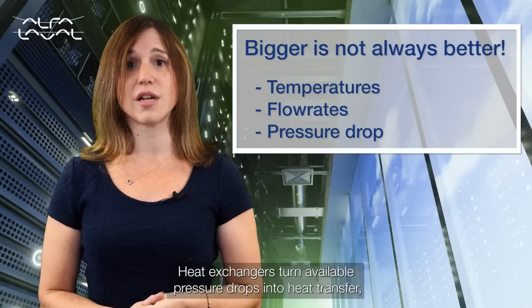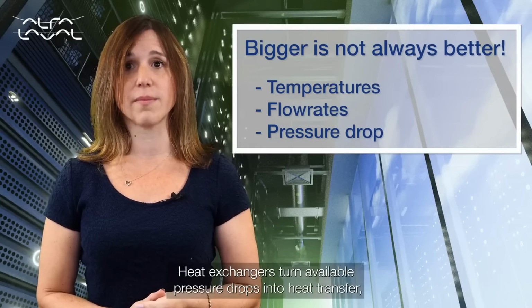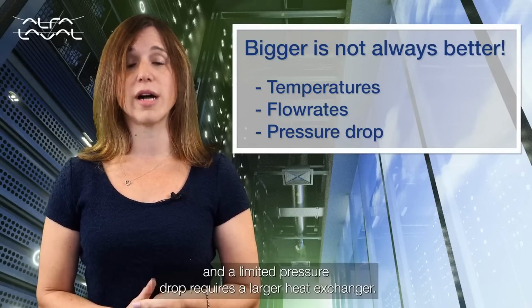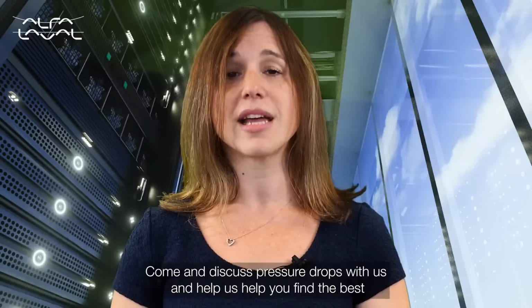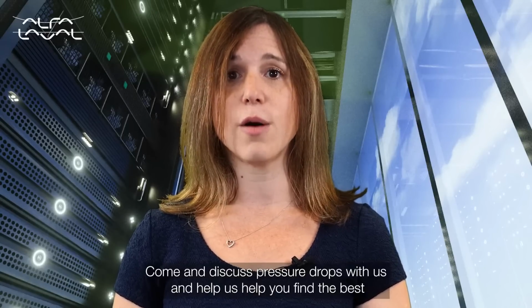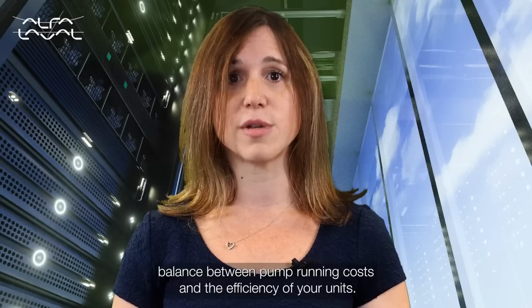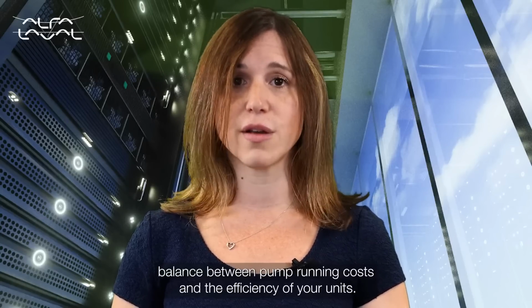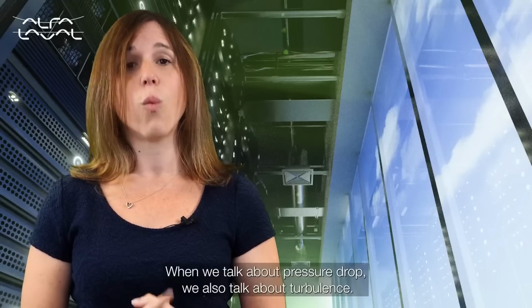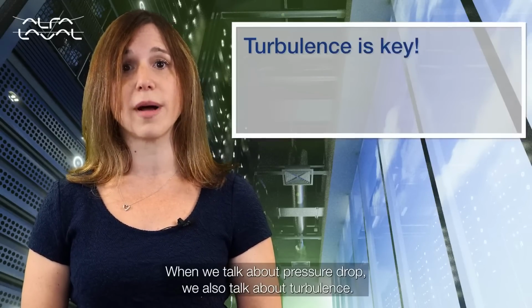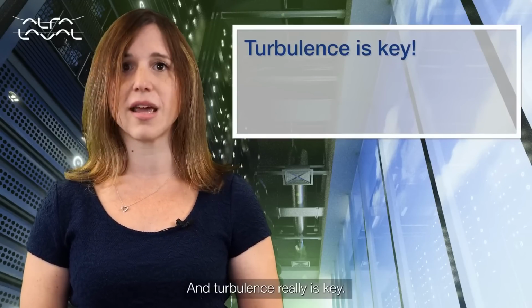Heat exchangers turn available pressure drops into heat transfer, and a limited pressure drop requires a larger heat exchanger. Come and discuss pressure drops with us and help us to help you find the best balance between pump running costs and the efficiency of your units. When we talk about pressure drops though, we also talk about turbulence, and turbulence really is key.